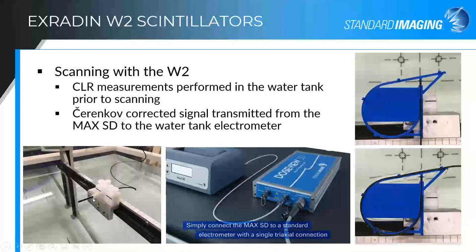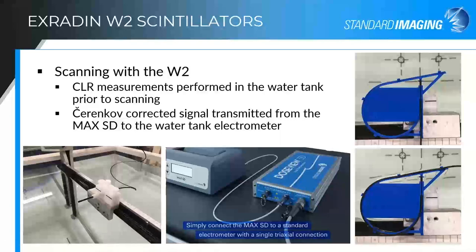The water tank setup uses an adapter sleeve to increase the stem size of the scintillator so it fits in a standard chamber holder. The fiber connects to the MaxSD input, and a triaxial output from the MaxSD goes to your water tank scanning electrometer. From the water tank's standpoint, it looks like a diode — a detector with no applied bias that produces a signal when the beam is on. You do need to scan slowly; it's a low signal-to-noise device, and we recommend about one second per measurement for much better data.